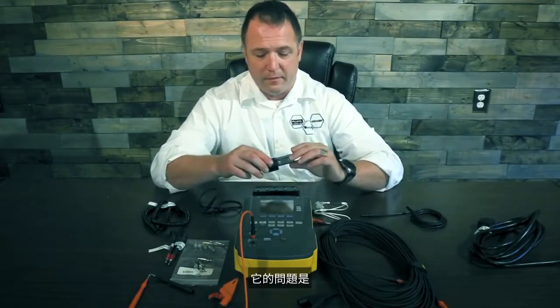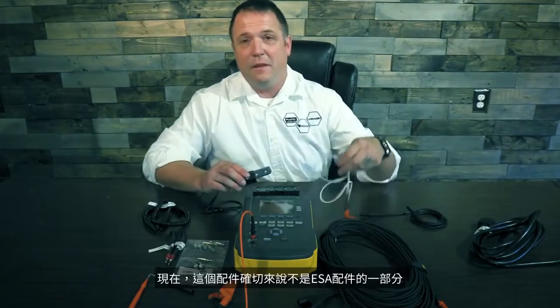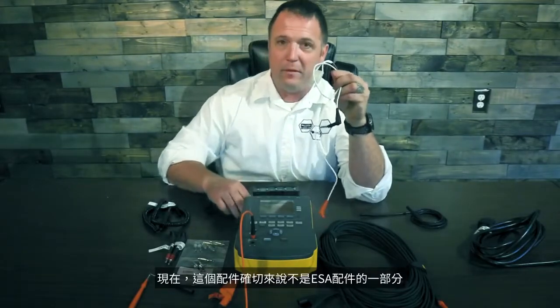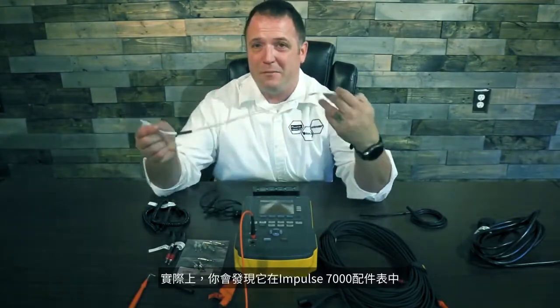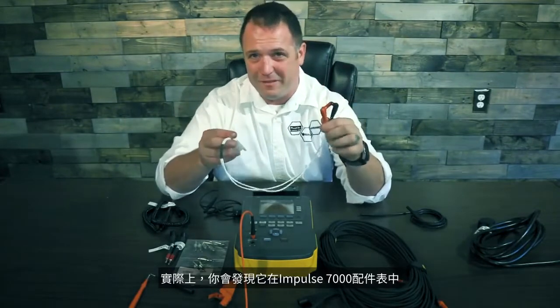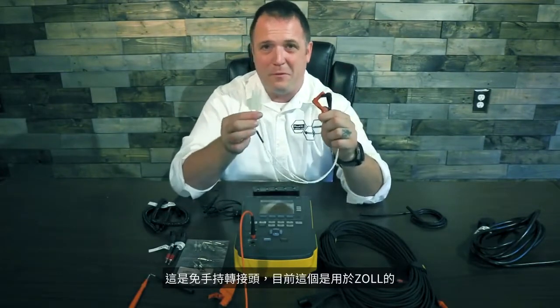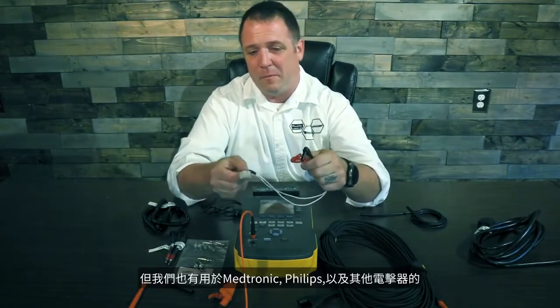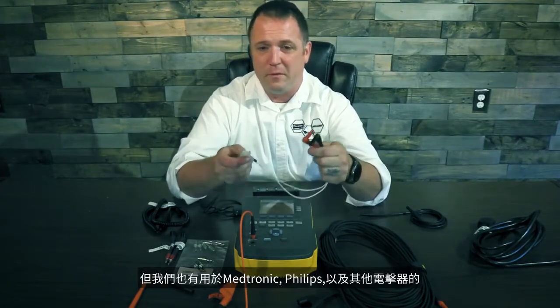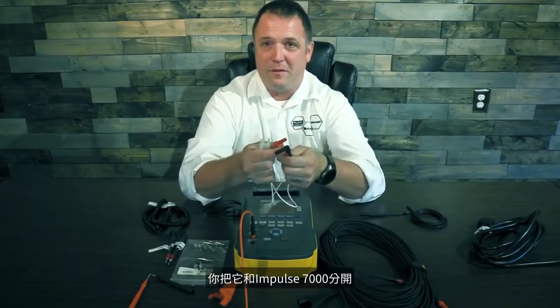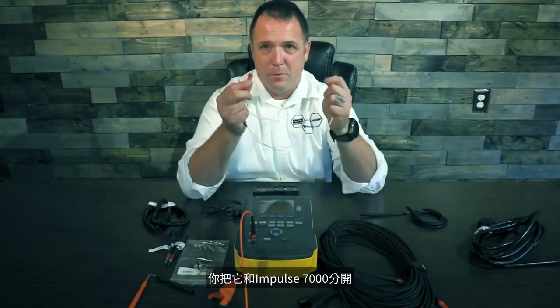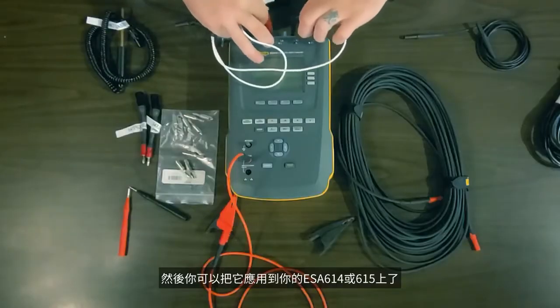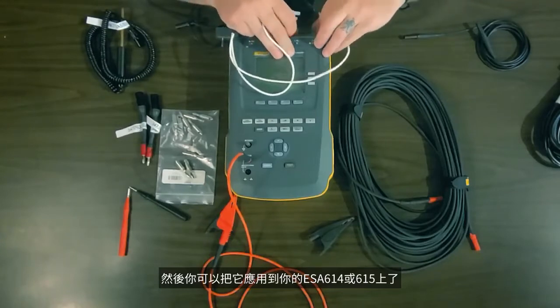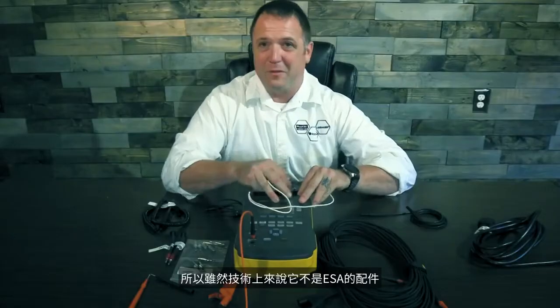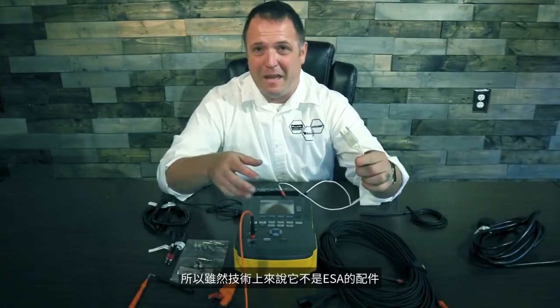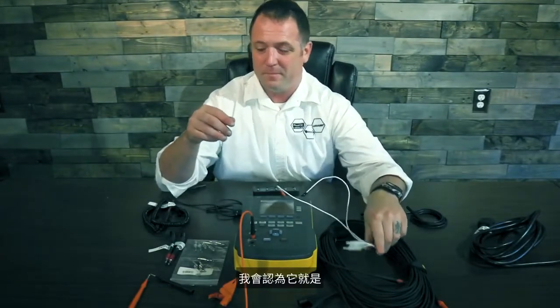The problem with that is we have to use another accessory. Now this accessory is not technically part of the ESA accessory kit. Actually, you're going to find it's under the Impulse 7000 accessories. This is the hands-free adapter. This one just has to be for a Zoll, but we also have them for Medtronic, Philips, and all the other defibrillators. So when you're done with the discharge test, you would disconnect this from the Impulse 7000, boop, and you can then apply it over here to your ESA614 or 615. So while it's technically not an ESA adapter, I'm going to consider it one.